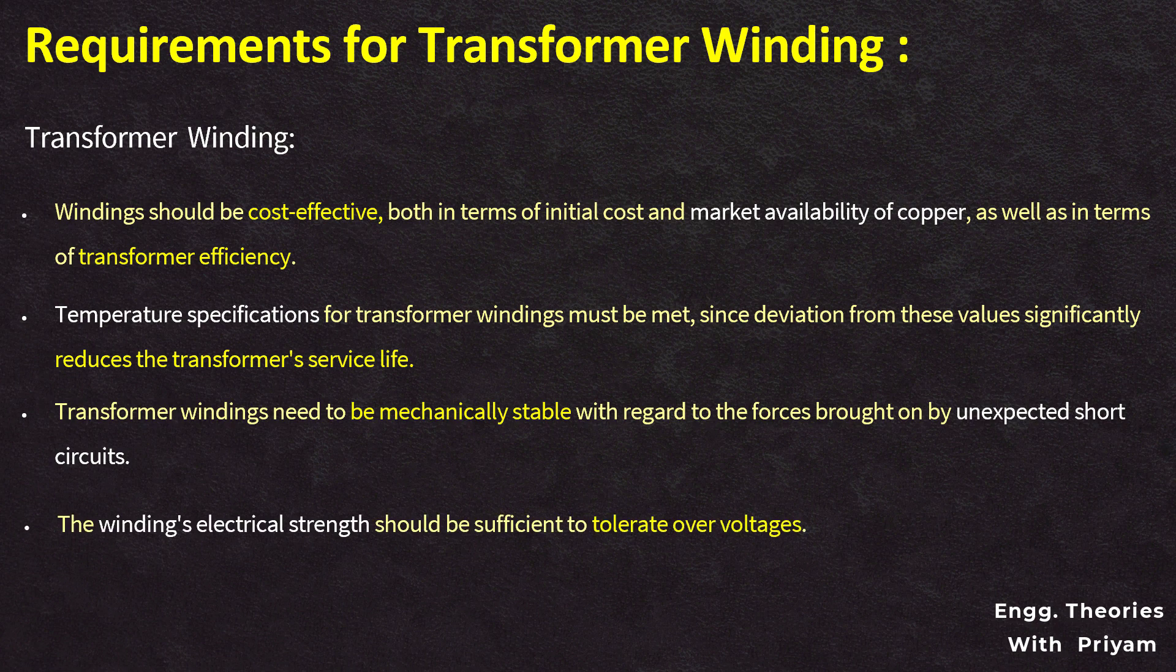The winding's electrical strength should be sufficient to tolerate over-voltages. These criteria often run counter to one another. For instance, a higher current density in the winding results in less copper being used, which causes copper loss or I-squared-R losses to rise and the efficiency of the transformer drops. Allowing a greater temperature rise in the winding results in a smaller transformer but a shorter service life. As a result, it is crucial to carefully plan the winding of a modern transformer, particularly when it comes to high-voltage transformers.